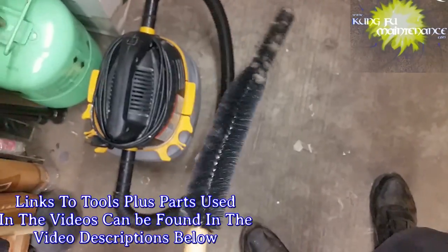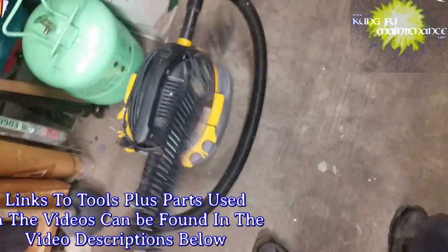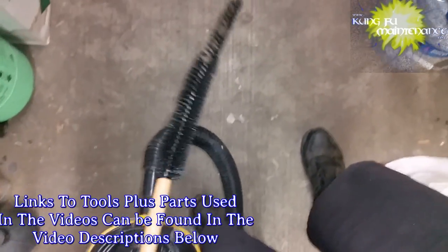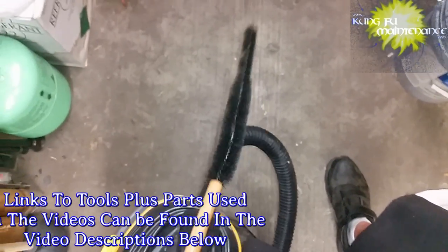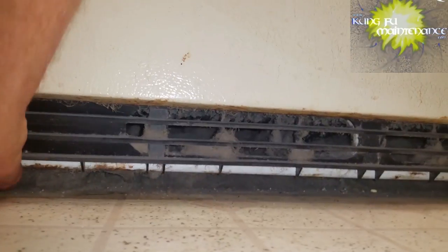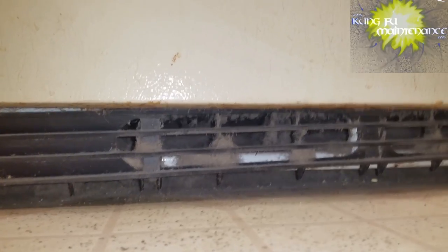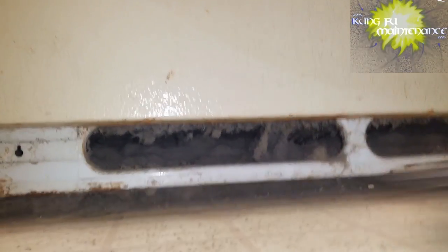But a lot of times if it's a dirty coil, it can make like a 7 to 10 degree difference. And that's enough for it to stop freezing ice cream. So it's kind of the first check. Yeah, so some refrigerator coils are located at the back of the refrigerator, and then some are below the machine, like this one. Below it.